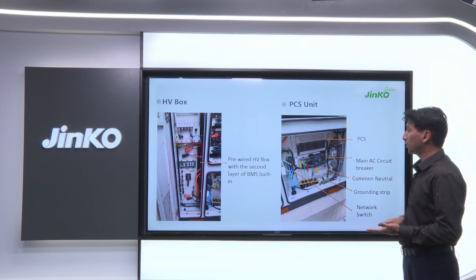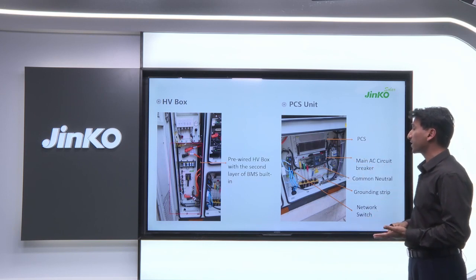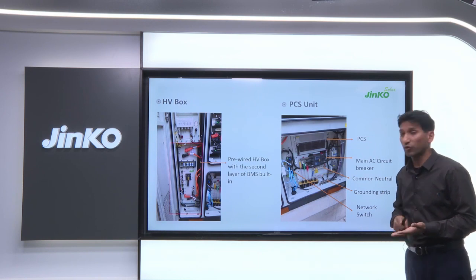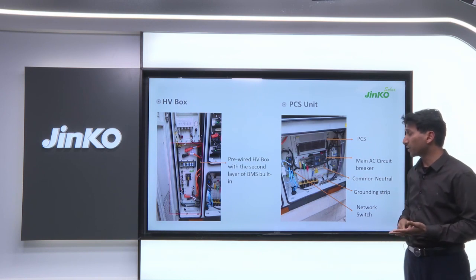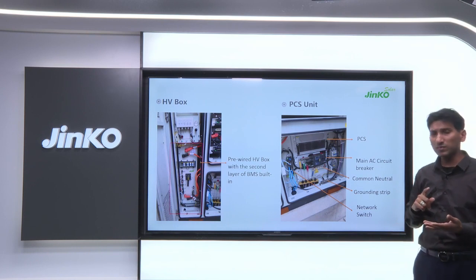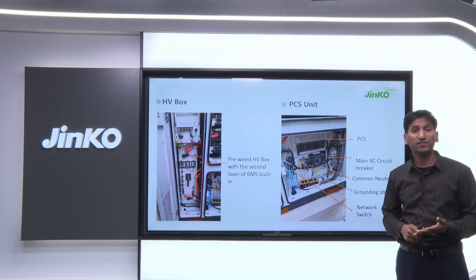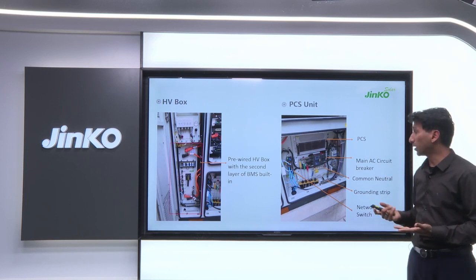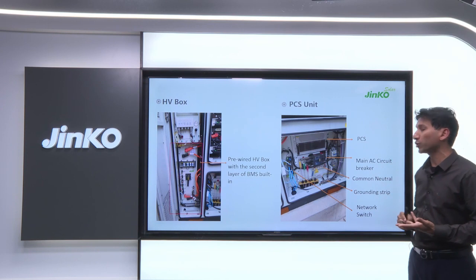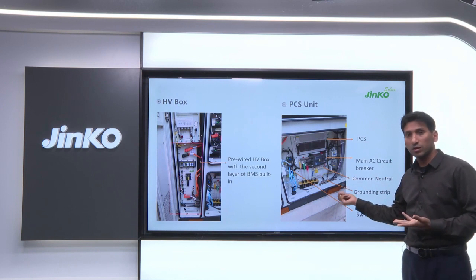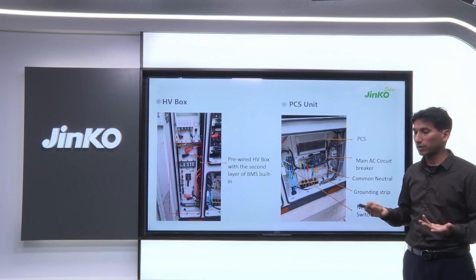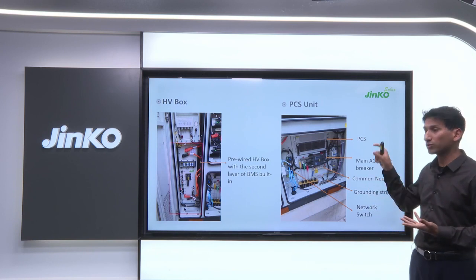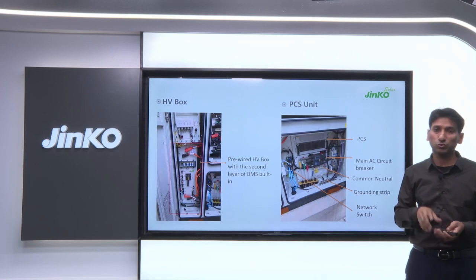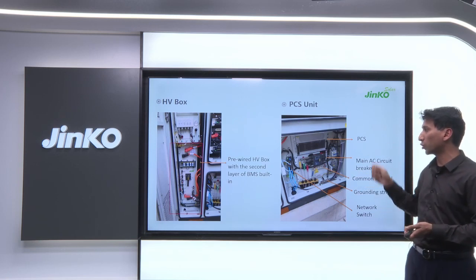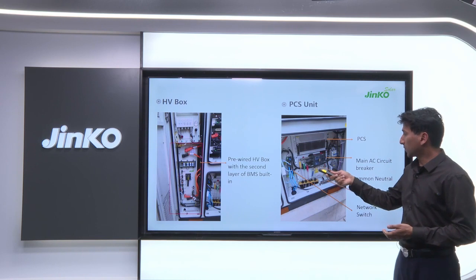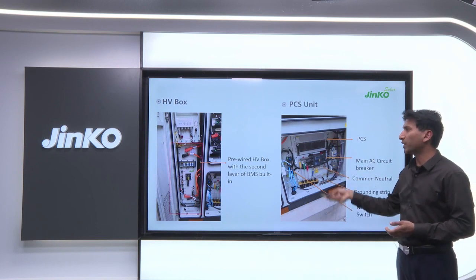It has a DC switch and many MCBs to control the units inside. Inside we have a second layer of BMS, which we call the BCU. We also have many contactors, sensors, and an AC/DC power supply. We need the AC/DC power supply because some equipments need a 24-volt power supply, but what comes from outside is 220 volt, so we cannot use that directly. We put a converter here and use the 24 volt to power those equipments.